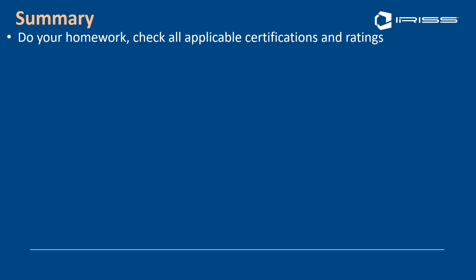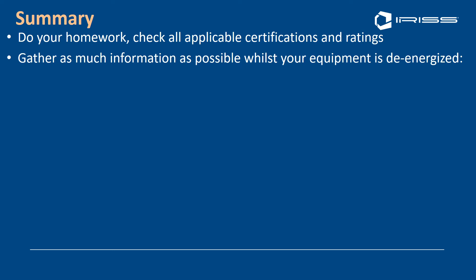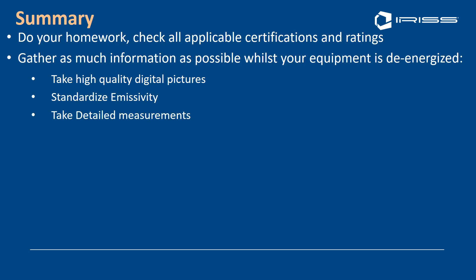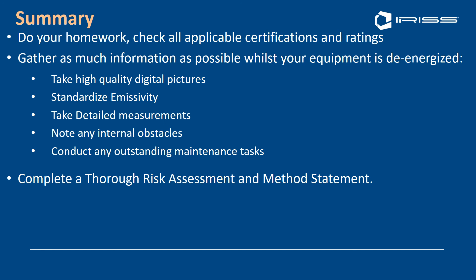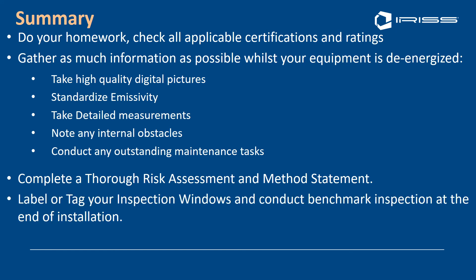In summary: do your homework, check all applicable certifications and ratings on the panels you're working on, and gather as much information as possible while equipment is de-energized. Take high-quality digital pictures, standardize emissivity, take detailed measurements, and note any internal obstacles — reinforcing on the door, cables running where you need windows — as this will dictate window placement and size. Conduct any outstanding maintenance tasks, complete a thorough risk assessment and method statement prior to the job, and label or tag your inspection windows.